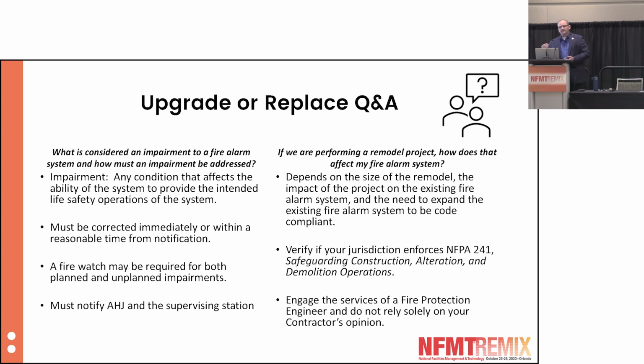Additionally, the service provider must notify the owner within 8 hours of an impairment, and they must notify the AHJ of that impairment. So now it's not just between you and the vendor. The vendor is required by code to go and tell your local fire department that your system is impaired. Now the pressure starts to mount for the facility manager.